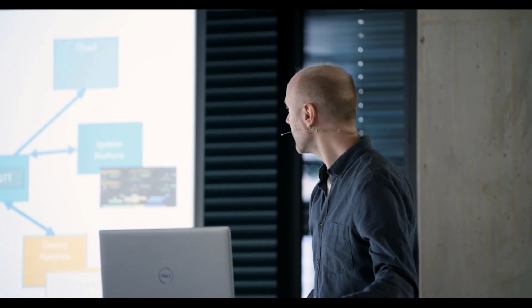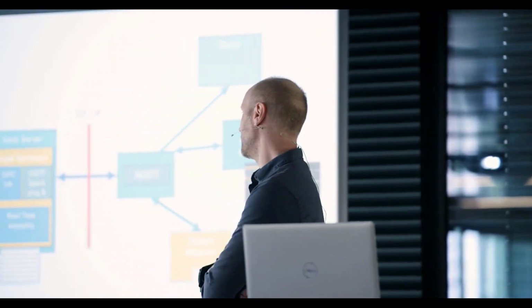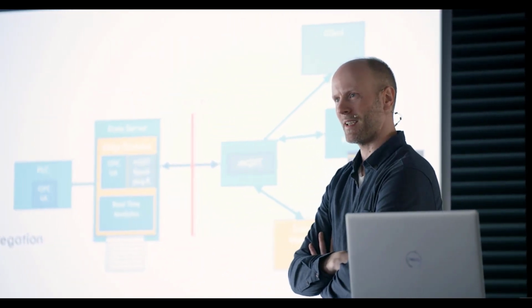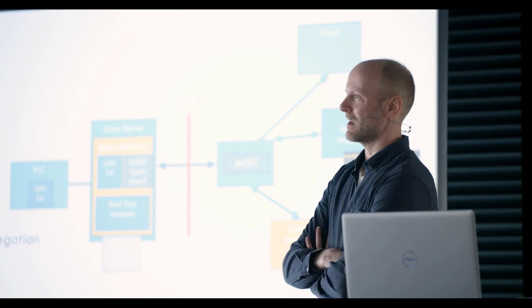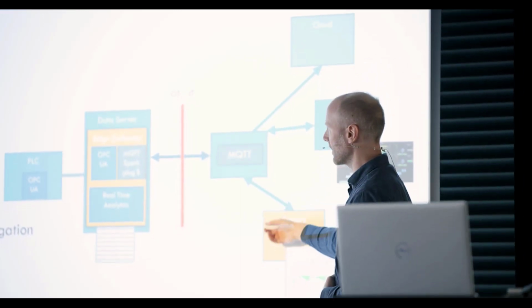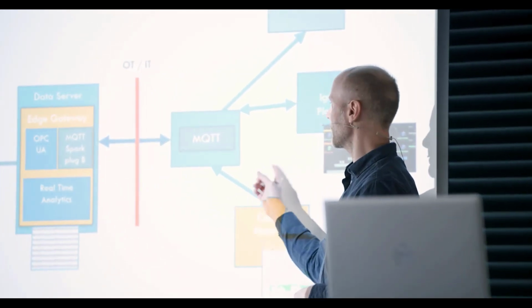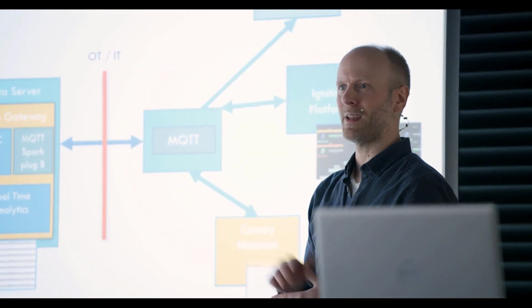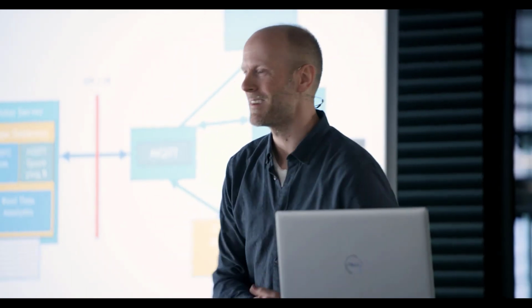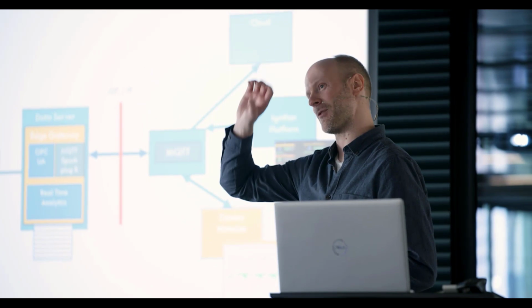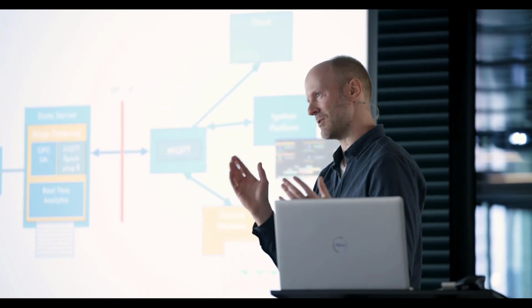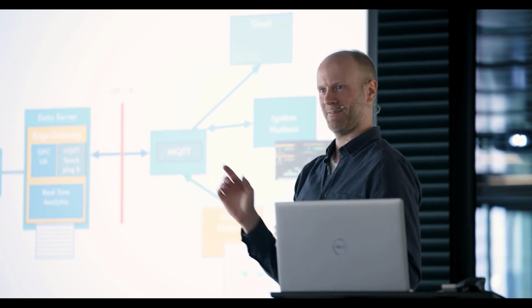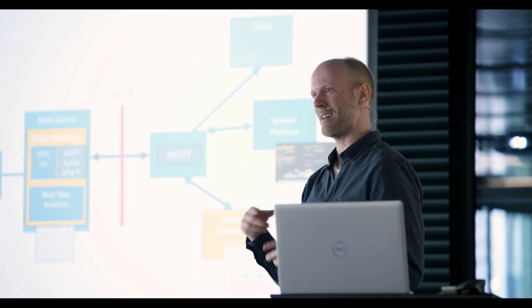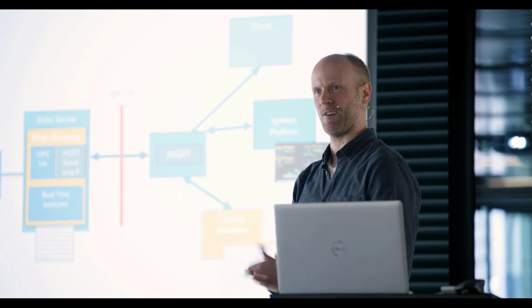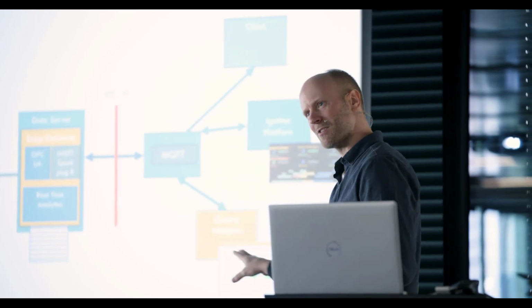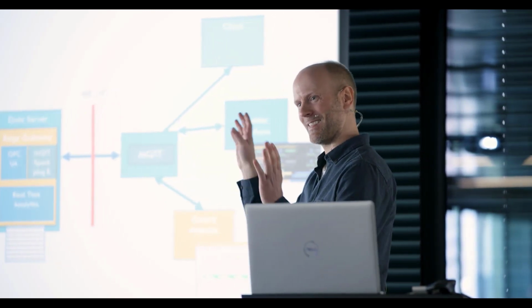Now over to the ugly. Something I call birth storms can happen. We had one instance where one of the Canary collectors was struggling with disconnects from the broker. So once every minute or two, it would disconnect and reconnect, and then ask for birth certificates from all our machines. That's about 300,000 tags - a lot of data. It would do that every minute, so it's not lightweight anymore - it's actually quite hard on the network. That eventually crashed the collector because of all that data.